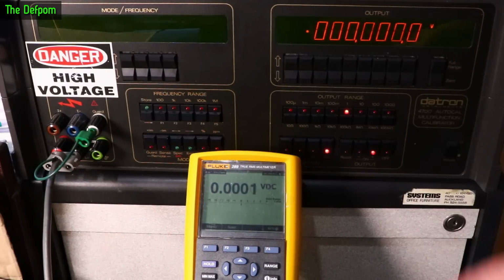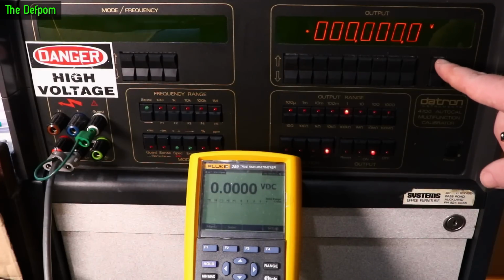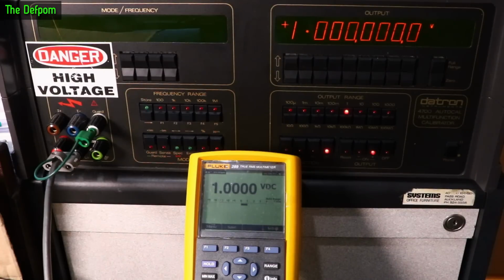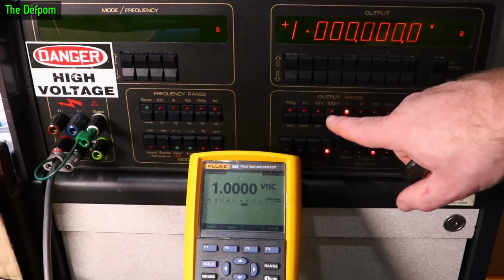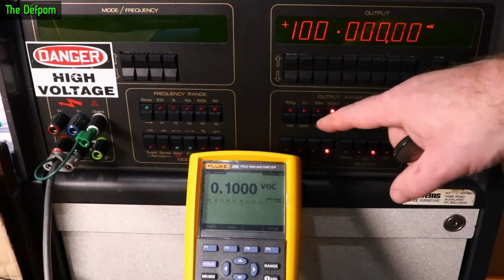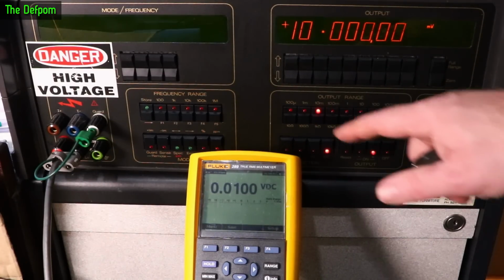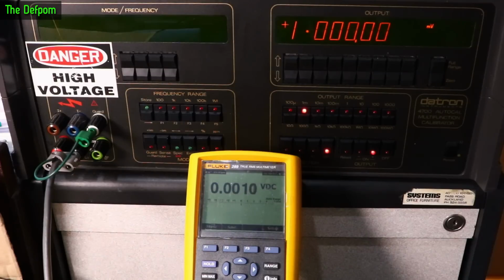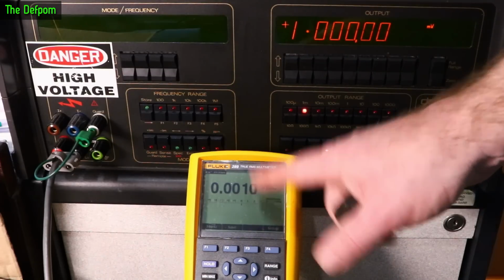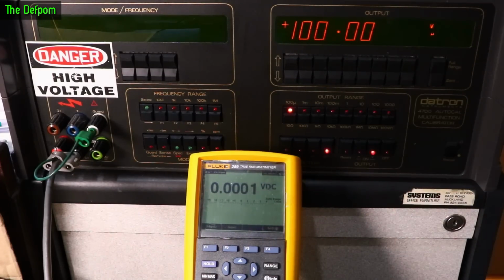So I should be seeing 0 volts here, and we basically are, with a little bit of rounding going on. 1 count sometimes flicks up. So let's do 1 volt. Look at that, perfect. I'm going to go downwards first. 100 millivolts is perfect. 10 millivolts is perfect. 1 millivolt is perfect. Don't forget you got that 1 digit flicking up before. 100 microvolts, perfect. So this is still flicking at 1 digit. So yep, that's looking really good.